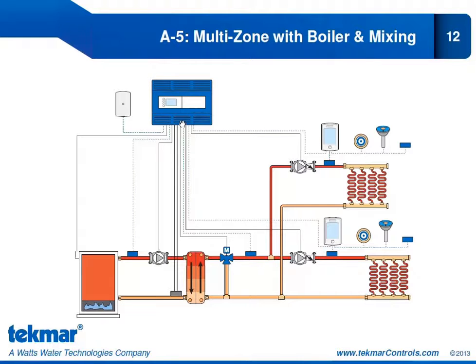The reset module will be operating the boiler. We'll be operating this boiler system pump here, and we'll also be operating the mixing device. And each of these zone pumps will be operated by the zone manager. So the 654s will be connected to the zone manager for that pump operation, and that's why we don't need any isolation relays in this case, because the pumps are not being directly controlled by the 654. You can see there is also a freeze protection aquastat, and that is again to protect the source side of the heat exchanger.